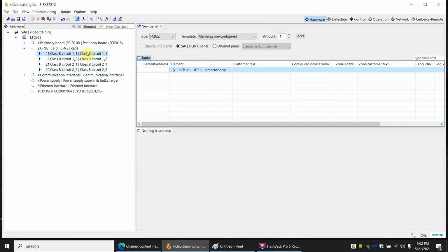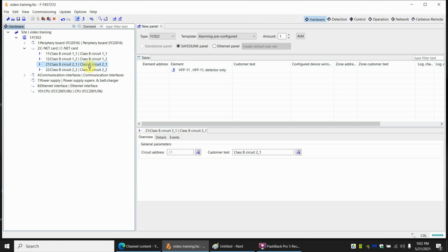If you had 4 floors and you stuck floor 1 on circuit 1-1 and floor 2 on circuit 1-2 and so on and so forth, and you came in a year later and you had a short circuit on circuit 2-1, you already know that you have a short either on the panel itself and you have damaged hardware at the panel, or more likely you have a bad device or a bad wire on the 3rd floor. Leave the 1st, 2nd, and 4th alone.